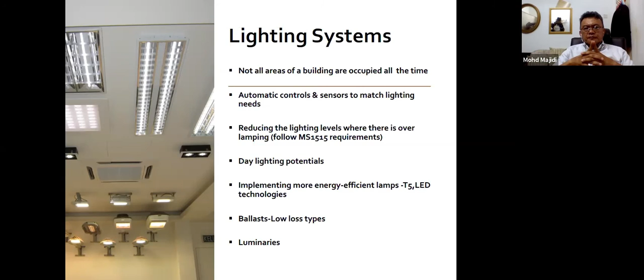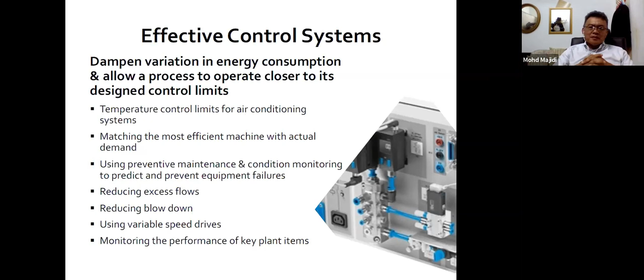Effective control is important because it's part of IoT, where you have everything in front of you and you're able to manage it. When everything is manual, people tend to ignore it. People assume that once you put in a timer, it works forever, but timers don't work forever. We have done audits where the facility teams were confident they had switched off everything at night, but when we went to the site at night, we noticed the timer controls were faulty, and equipment was being left on that everyone assumed was switched off automatically by the timer. So it's important to make sure all your sensors are operational, as this is part of the day-to-day activities of energy management, which impacts maintenance requirements, as mentioned by Mr. C earlier this morning.